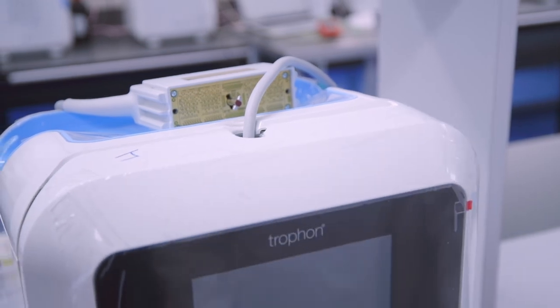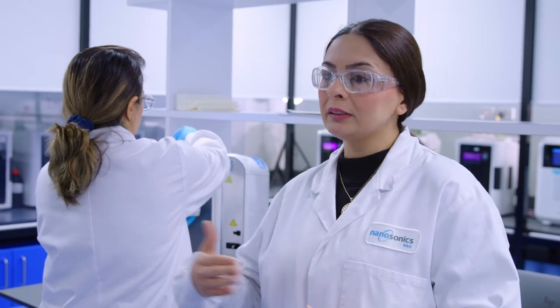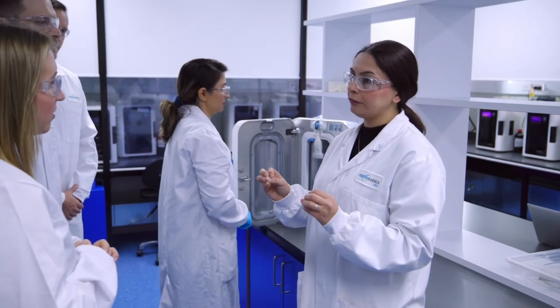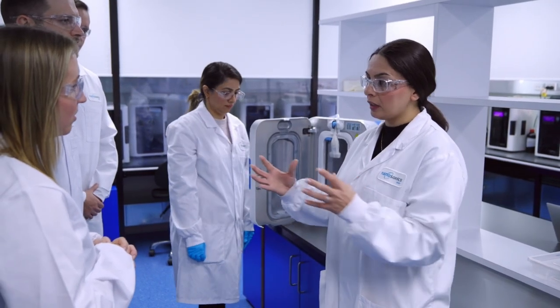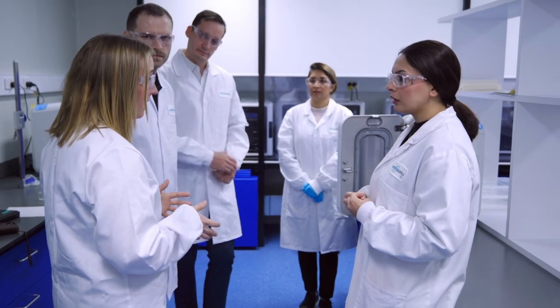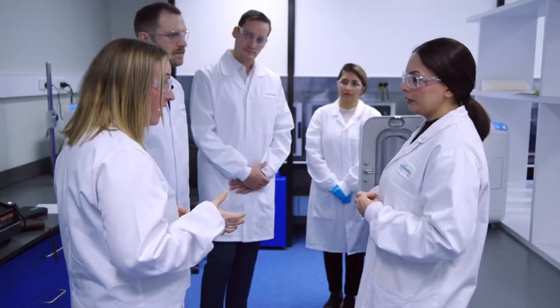And the next step is to check the temperature of the probe surface during the cycle. What we do is go with the worst case scenario. So we run 2 back-to-back cycles to make sure that if this is what happens in the field, like very quick reprocessing, it doesn't exceed the limit. Okay, so you're taking into consideration the fact that a probe can be reprocessed over and over again in a single day. Yeah. And you want to make sure it doesn't melt, essentially.